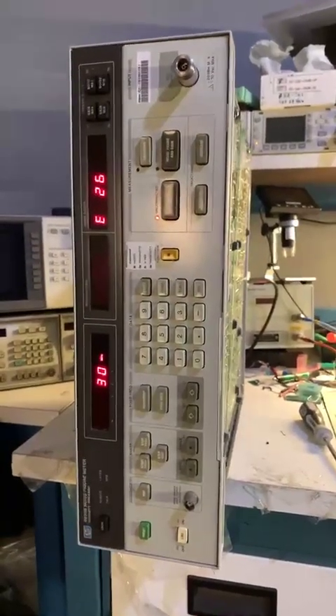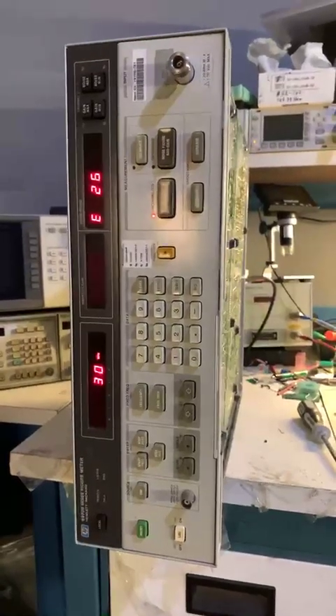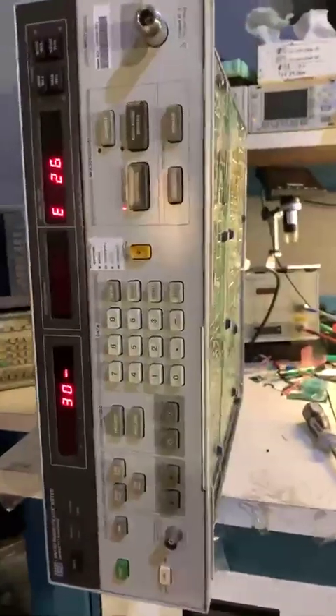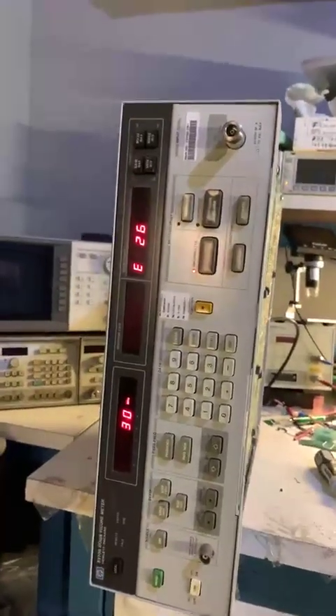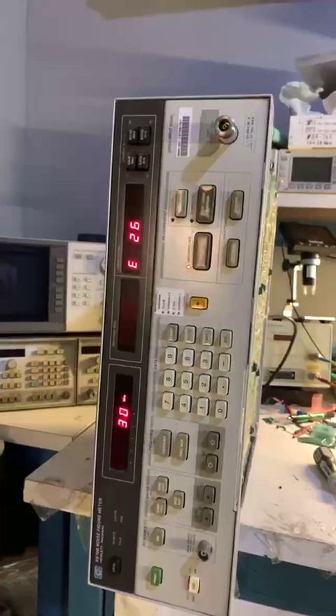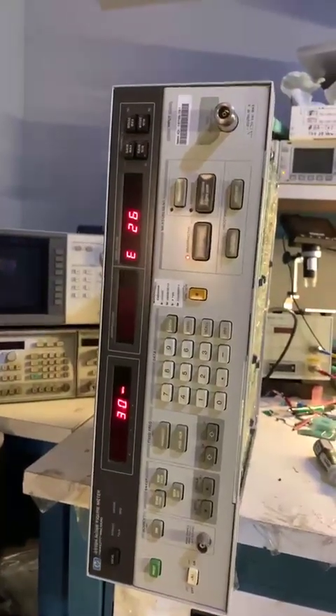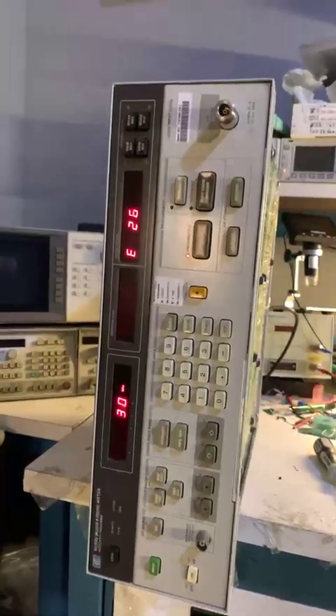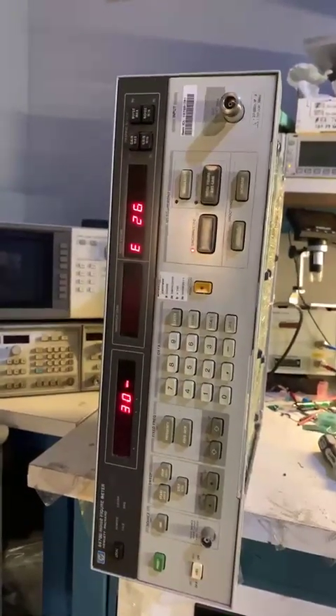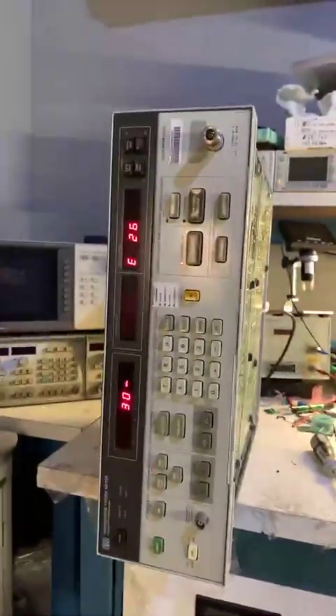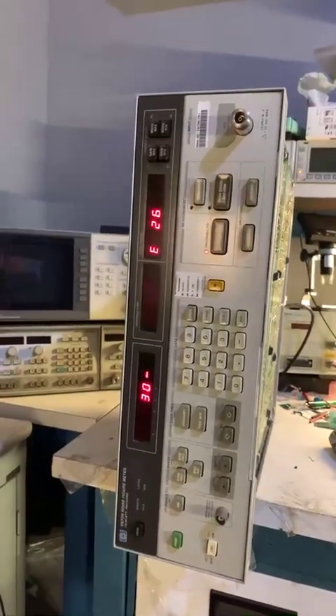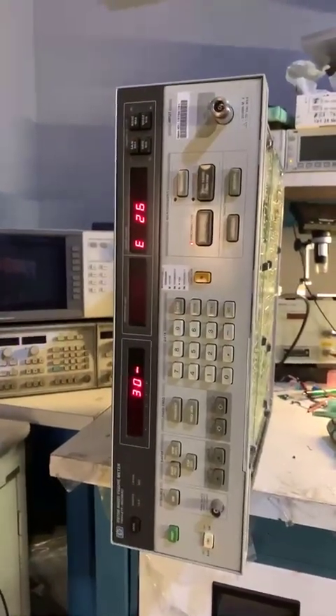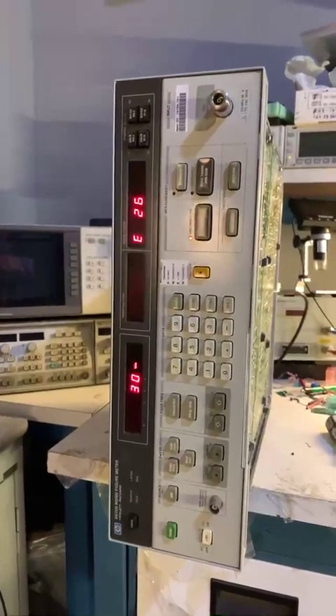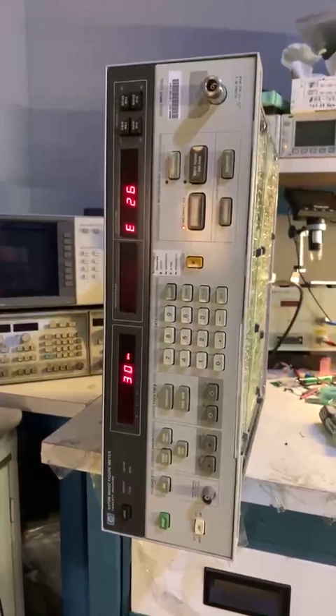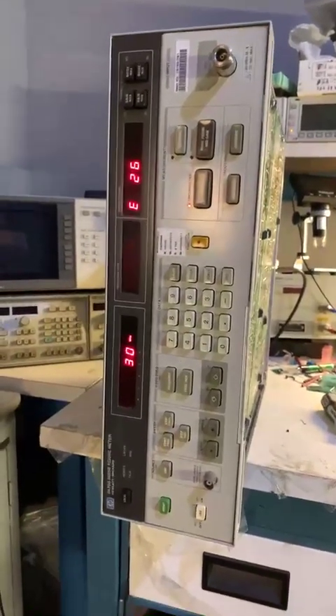So this unit has a lithium cell built in that pretty much retains the calibration memory when you turn the unit off, and it's just a 3-volt lithium cell that resides on the controller board. And pretty much what the calibration memory holds is the calibration values for the IF attenuator, but also if you store noise source tables, ENR tables, then those also are stored in calibration memory.